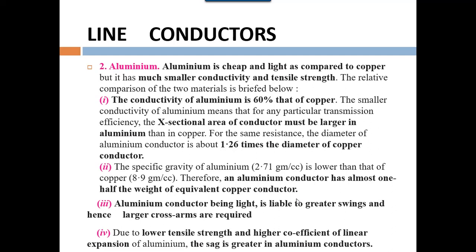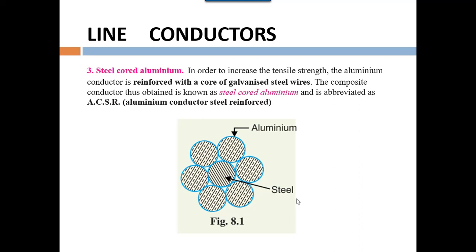If we increase the cross-sectional area of aluminium, its conduction will increase. Comparing aluminium and copper for the same current-carrying capability, the aluminium diameter is 1.26 times greater than the copper diameter. The specific gravity of aluminium is lower than copper, therefore an aluminium conductor has almost one-half the weight of the equivalent copper conductor. However, aluminium conductor being light is liable to greater swing and hence larger cross arms are required. Due to low tensile strength and high coefficient of expansion of aluminium, the sag is greater in aluminium conductors.